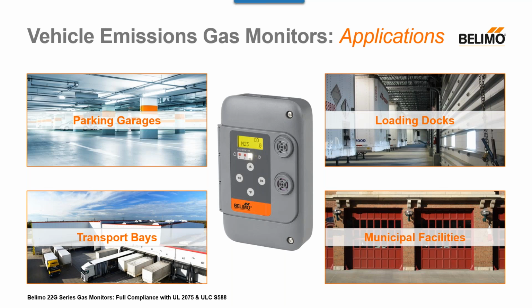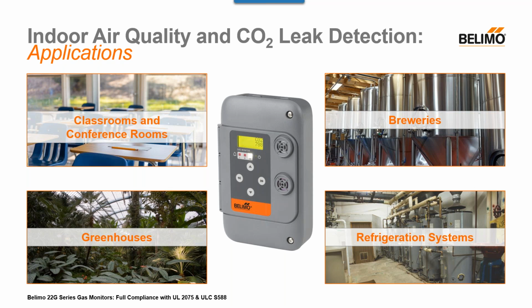Common applications for vehicle emissions include enclosed parking garages, loading docks, transport bays, municipal facilities, boiler rooms, and basically anywhere where combustion is present. Common applications for air quality monitoring, usually around 2000 ppm, include classrooms, conference rooms, and warehouses. Applications to monitor for CO2 leaks include breweries, greenhouses, and CO2 refrigeration systems, which carry slightly higher ppm levels of 5,000 and 10,000.